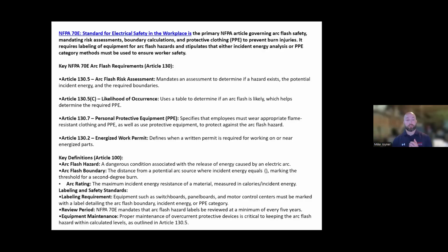So electrical equipment, proper maintenance of the overcurrent protection devices, is critical to keeping the arc flash hazard within calculated levels. That's what we're talking about in conjunction with NFPA 70E and 70B. You have to maintain your equipment properly to ensure the ratings of the arc flash study. If you don't maintain your equipment properly, the arc flash study is not going to be accurate, which is going to lead us into the next slide.